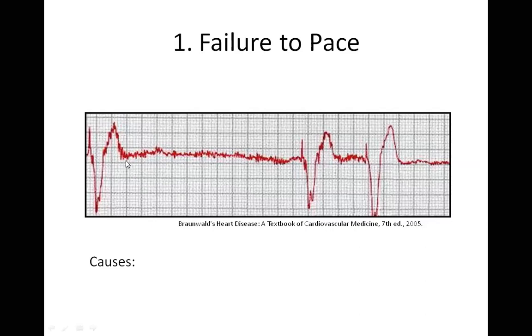Okay, good. So I want you to look at this slide very well. You see all this baseline reading, these artifacts. Can you see this artifact? Yes, Chief. It is sensing it as a native activity. The pacemaker was sensing this, thinking this is the patient's normal electrical activity. That is why it was inhibiting all through. So this artifact was sensed by the pacemaker as intrinsic activity, and that is why it was inhibiting pacing all through.